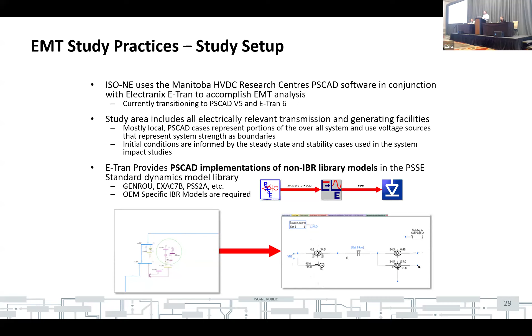Moving forward, once we have our cases set up, we put a lot of engineering judgment into what we're going to run on these cases. Interconnection system impact studies require full N-1 and N-1-1 analysis, but the decision on which specific faults to run is really up to the tech lead and the engineering folks running the study.